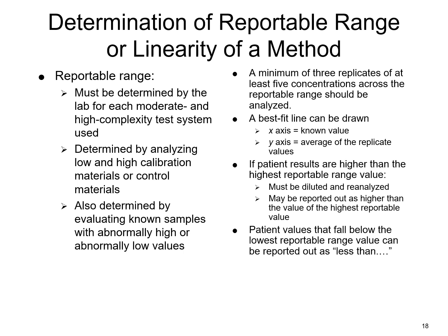If the patient's results are higher than the reportable range, then some kind of modification is going to have to be done, some sort of dilution, or you rerun it. And of course your laboratory would have to determine, are you going to do the dilutions, do the equations, or is it just something that you can report out as greater than or less than? But your patient values have to fall within the limits of whatever is set. So once you determine this is the lowest point that this machine can read and be accurate, and this is the highest point it can read and be accurate, then you know that your patient values have to fall within that range.